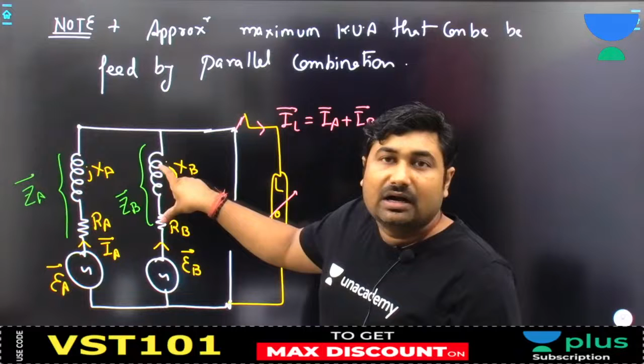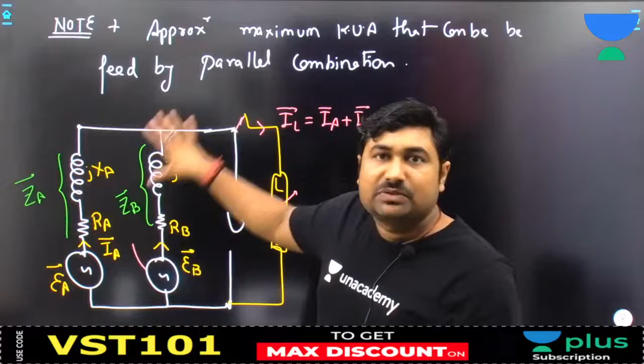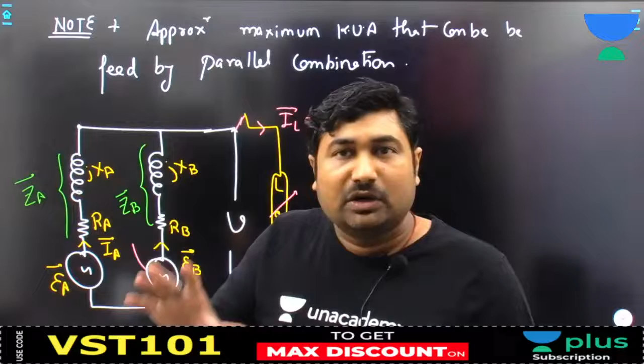Again, if EA and EB are equal, and if we increase the load, current IA and IB increase. More current will be supplied by the transformer with lower impedance, because current always tries to flow through the low impedance path. So that transformer feeds more current, which means it will get overloaded first. Please write this down. Are you able to understand? Yes sir.